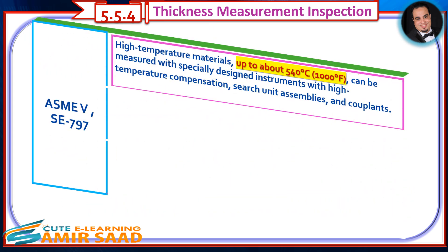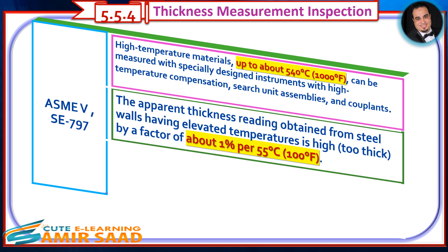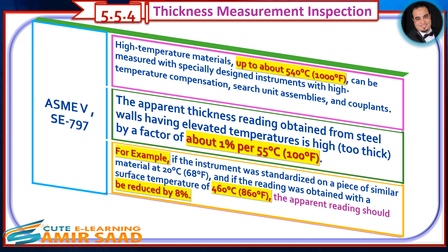As per ASME Section 5, SE-797, high-temperature materials up to about 540°C (1,000°F) can be measured with specially designed instruments with high-temperature compensation, search unit assemblies, and couplants. The apparent thickness reading obtained from steel walls at elevated temperatures is high — too thick — by a factor of about 1% per 55°C (100°F). For example, if the instrument was standardized at 20°C (68°F) and a reading was obtained at a surface temperature of 460°C (860°F), the apparent reading should be reduced by 8%.